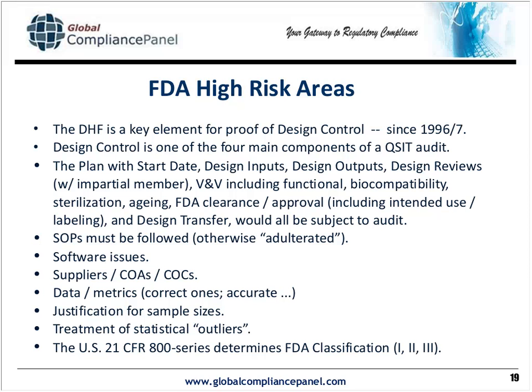I'm amazed at how many big companies have tried to fight the FDA on this. Their product is safe, it's effective, it works, the buying public likes it, and yet the FDA says it's adulterated. And the reason why? Because the company cannot show by its documentation that they followed their own SOPs and other documents.